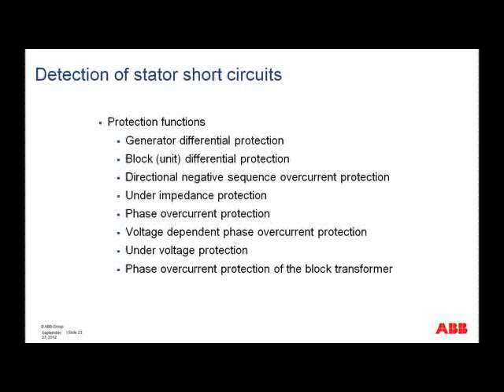Directional negative sequence overcurrent protection, under impedance protection. We have the phase overcurrent protection, but this is really not so common because, you know, for current that is fed from the generator to the fault, this current will decrease over time, and we will have a look at that a little bit later. So what is maybe more common for current that is being fed from the generator is to have this voltage-dependent phase overcurrent protection, under voltage, and also the phase overcurrent protection of the block transformer. Now this is an overcurrent protection that is measuring current fed in from the system to the fault.